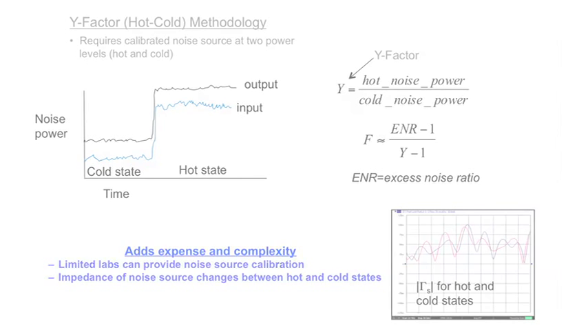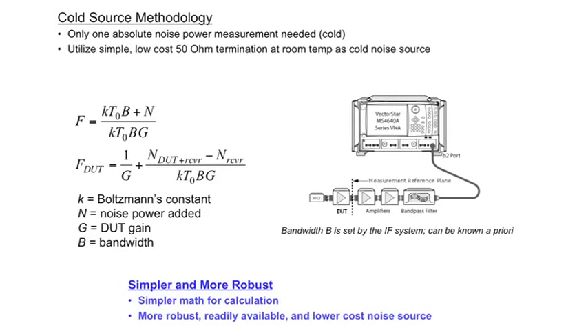The Anritsu VectorStar's Option 41 utilizes the cold source noise figure measurement method. It was developed to eliminate the requirement for a multi-state noise source, which would allow the use of a simpler, better controlled noise source, like a termination at room temperature. In that case, the noise figure is found from a more easily populated equation.